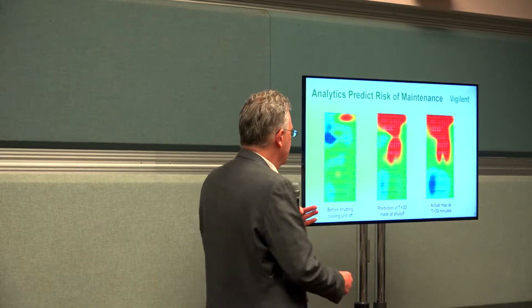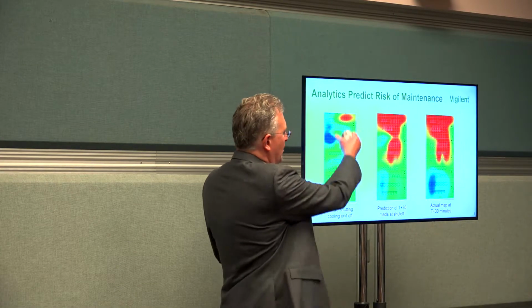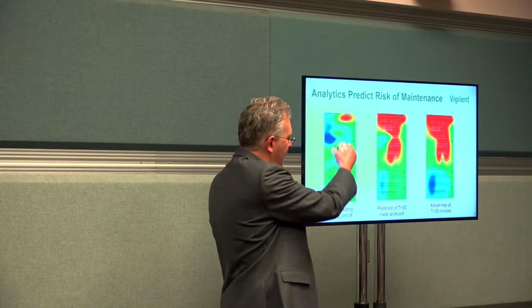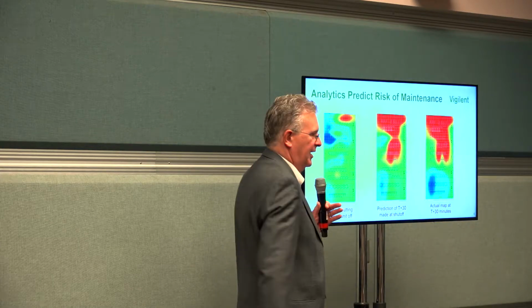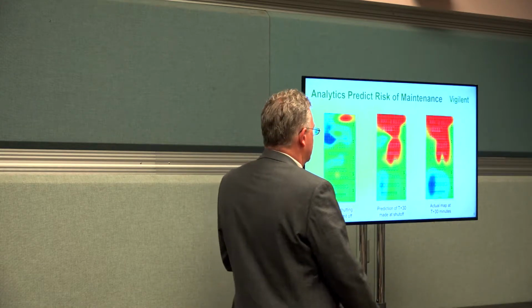Other than dynamically controlling cooling, the system also has insights that help people manage data centers. Here's a simple example: a data center where most of it is green and blue, so everything's fine. But people sometimes turn off air conditioners and can run into major problems because they don't know exactly what's going to happen. Here in the middle, the Vigilent analytics has determined exactly what the thermal impact of turning off that air conditioner for maintenance would be.